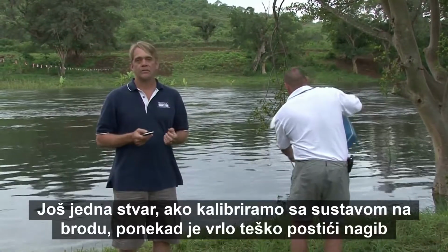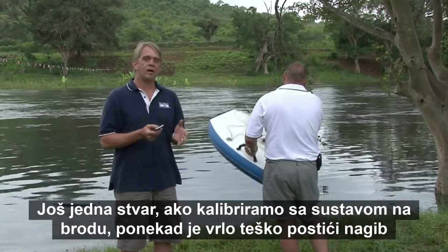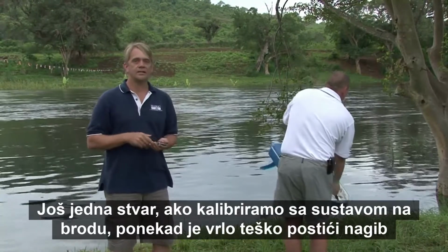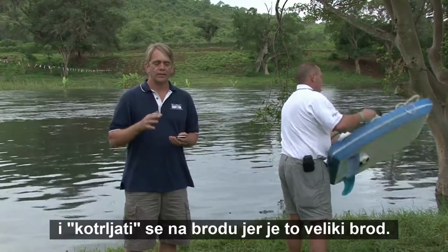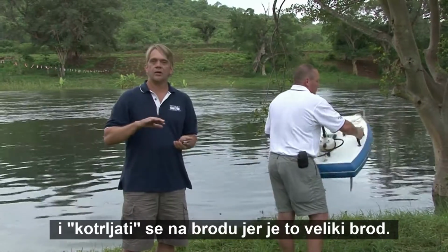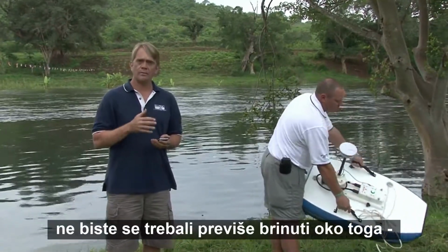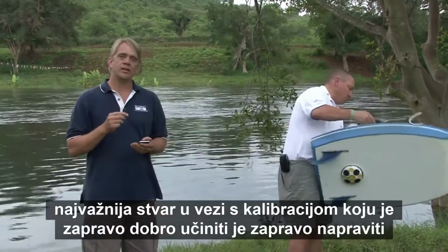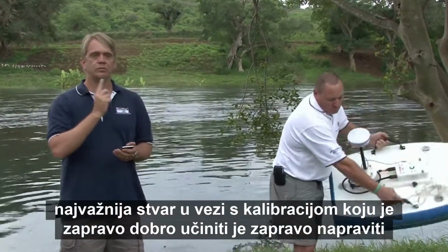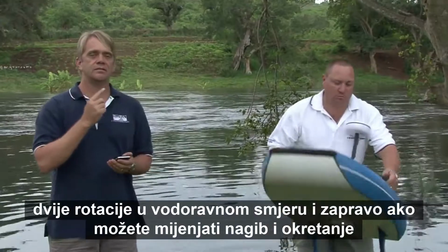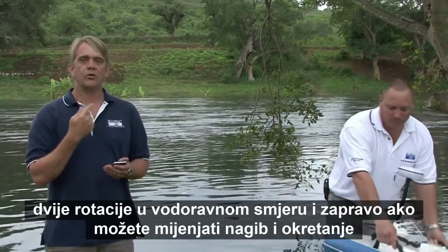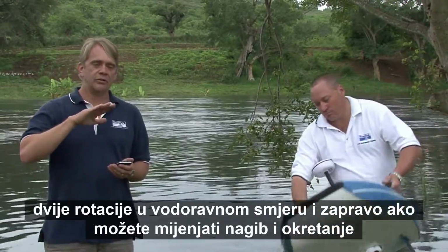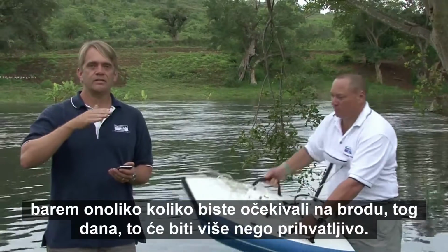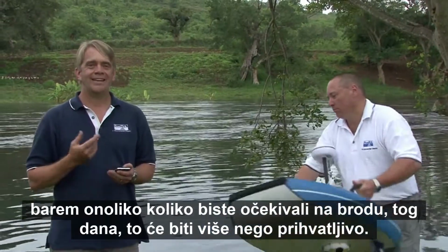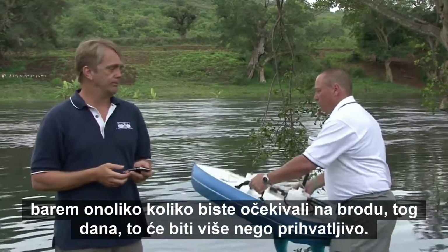Another thing, if we're calibrating with the system on a boat, sometimes it's very hard to get the pitch and roll on the boat because it's a large boat. But you shouldn't worry about that too much. The most important thing about the calibration is actually to do 2 rotations, okay, in the horizontal. And if you can vary the pitch and roll by at least as much as you would expect on the boat that day, that will be more than acceptable.